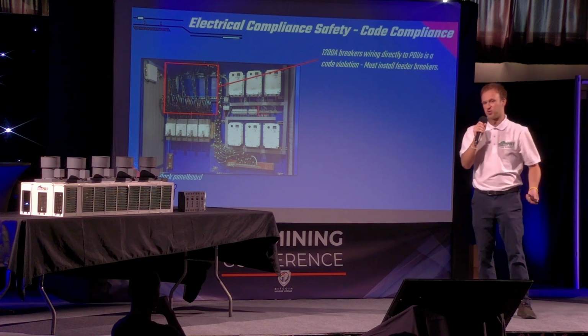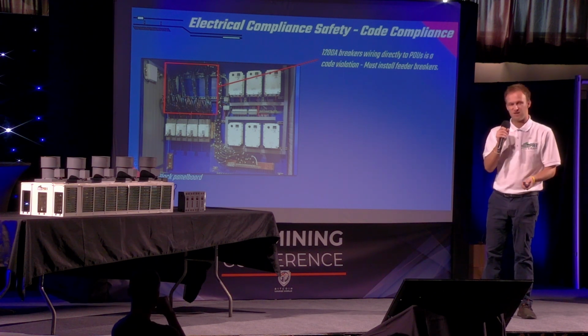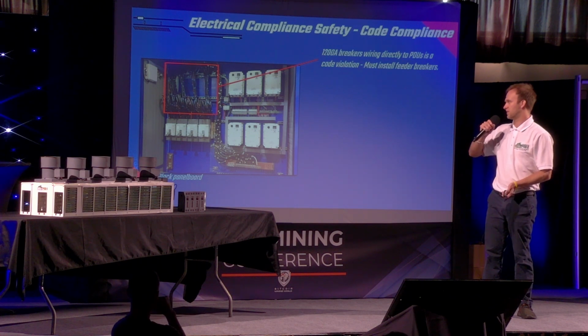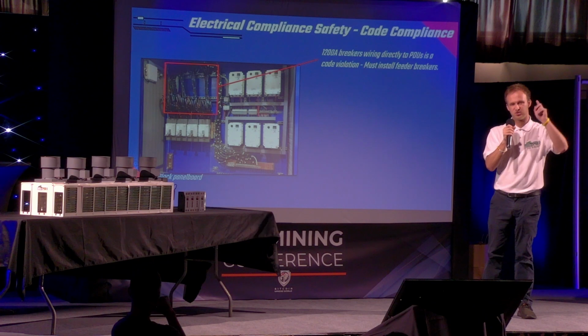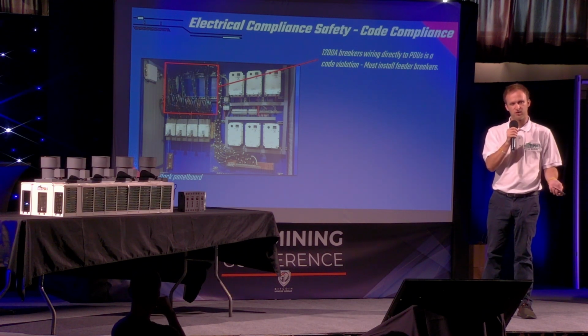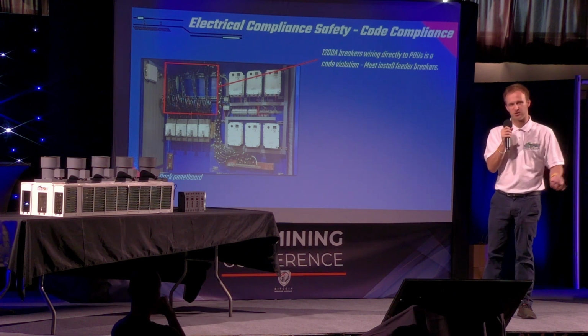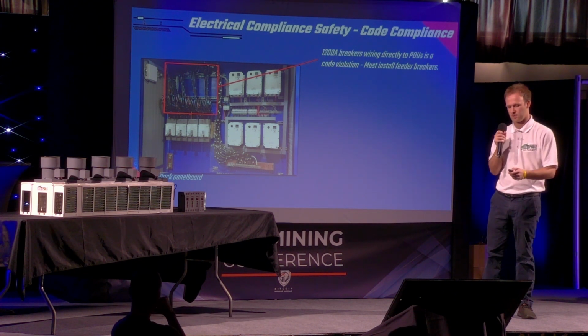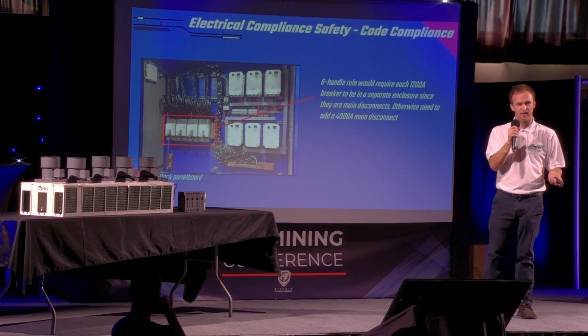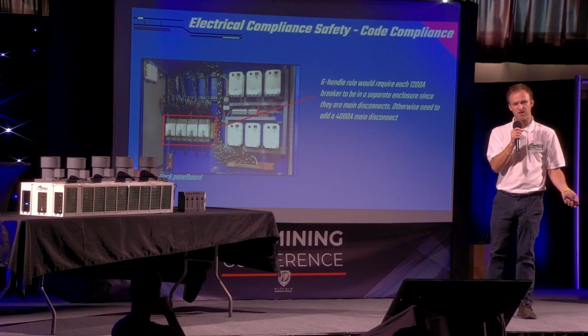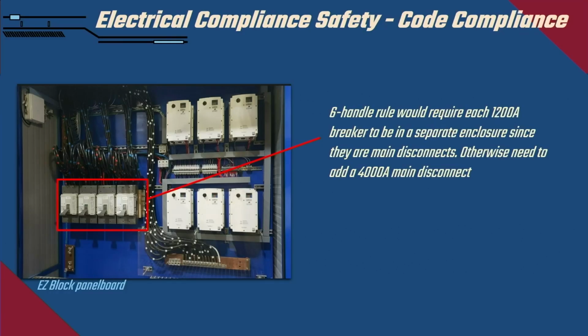These 4 breakers right here are 1200 amp main disconnects in this pod, and they are feeding directly to the PDUs inside of the pod, which would be a code violation because there are no upstream breakers on those PDUs. You have to have breaker protection on your equipment if they're feeding directly to your mains, or it's going to be a code infraction. Similarly, the 4 1200 amps are not allowed to be in the same container as each other because they're main disconnects. This violates what's called the 6-handle rule, and I believe they changed the code in 2017 because originally this was allowed, but now it's not. If these are main disconnects, they have to be in separate enclosures from each other, so you would have to move them either to their own 1200 amp panel boards, or you could add an upstream main disconnect to these 4 breakers, in this case a 4000 amp.